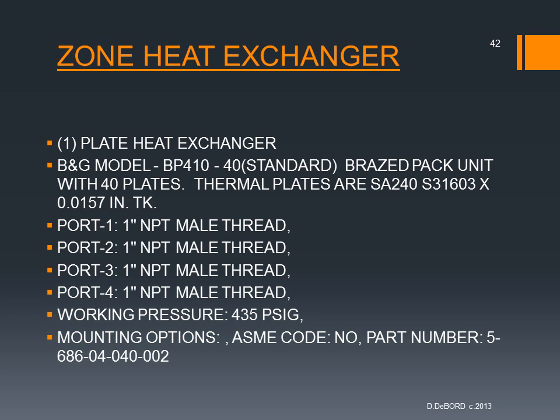So they're all going to need a heat exchanger. It's a plate and frame heat exchanger. And those are sized based on the load. In this case, we have 40 plates. You might have more plates depending on your loads or less. I would consult with the manufacturer when you're following these approaches to make sure that you have everything set up properly. These are from Bell & Gossett, and they are the originators of the system, but anybody else, your other manufacturers, should be able to help you also.